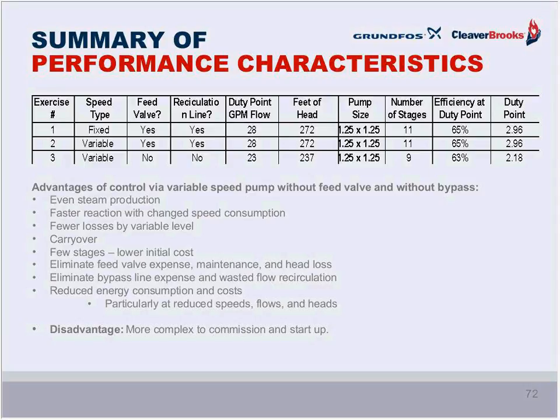And because the pump operates usually well below the 23 gallon a minute duty point, remember it goes back towards the left-hand side of the curve, where with our proportional pressure control, we have reduced head and reduced power consumption. So if you recall, in the 2 curves we showed you earlier when we compared fixed speed and variable speed with feed valves and recirc lines, you get the same variable speed benefits back at those low flows with this 3rd selection example.